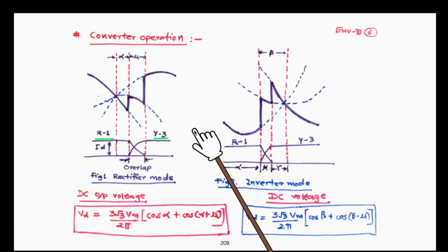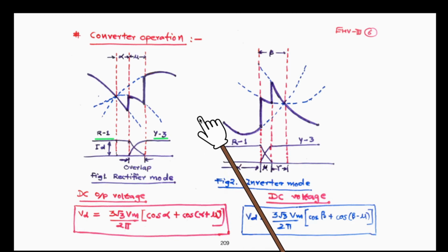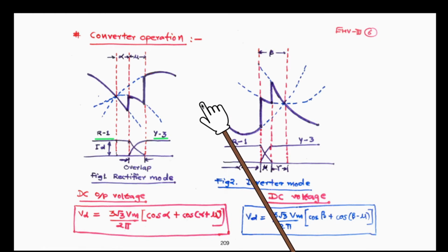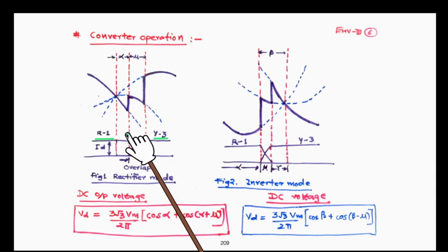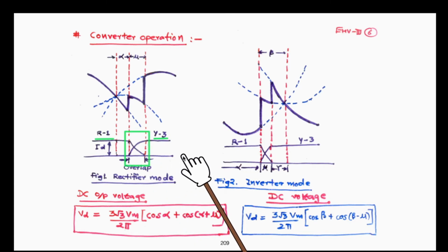In the three-phase bridge, if you remember, there are three legs of thyristors. The top layer of thyristors is numbered 135, and the bottom layer is 462. At any point of time, in the absence of commutation overlap, only two thyristors conduct. But whenever there is a commutation overlap, due to the source inductance on the AC side, that leads to the overlap, which is also indicated here. That is very common, and inductance is inherently present in all AC networks.